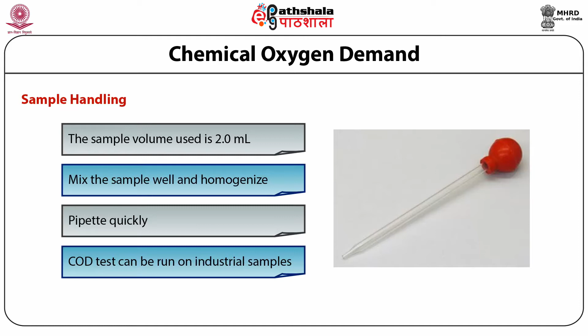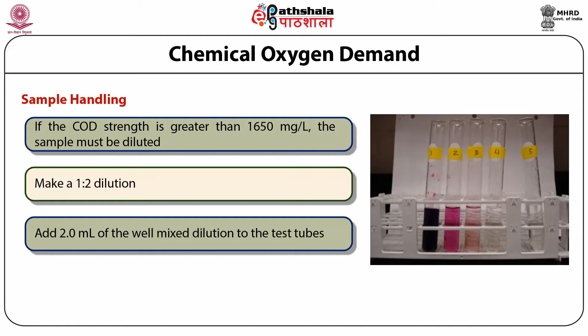Sample handling. The sample volume used for the COD test is 2 ml, so measuring the sample volume is critical. Be sure to mix the sample well and homogenize if necessary. Pipette quickly to avoid settling errors. COD can be run on industrial samples that may have high BODs. If the COD strength is greater than 1650 mg per liter, the sample must be diluted. We prefer to make a 1:2 dilution by measuring 50 ml of the sample and adding it to 50 ml of deionized water. After that, we add 2 ml of the well mixed dilution to the test tube.